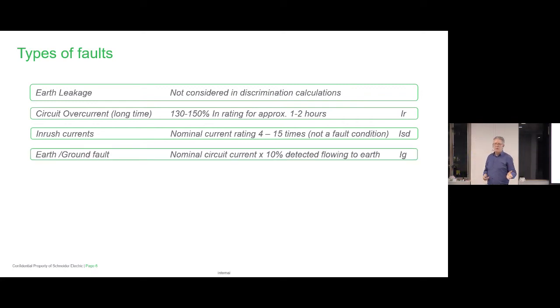Ground fault, another one. Often that is done separately, but it is more and more done in the breaker as well. And that's often around about 10% detected ground fault current. You'll see to the right there, I put the international terms, which are Ir, Isd, Ig. These are IEC international terms, so you'll see those everywhere. You'll see them on breakers, so you know what they are.